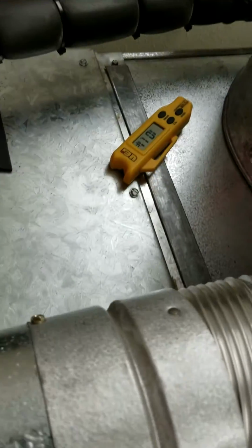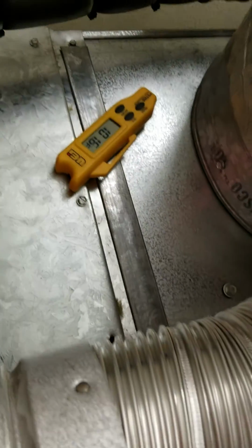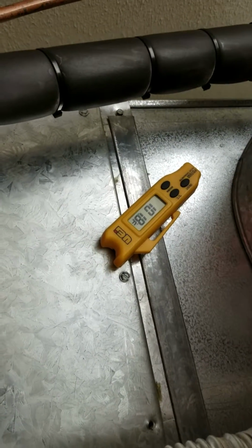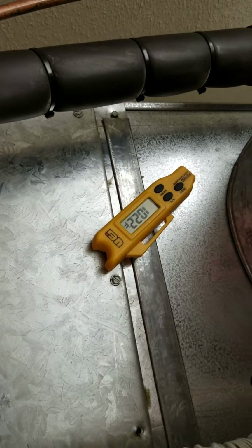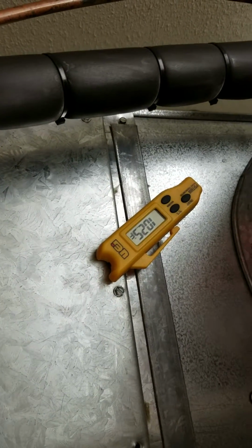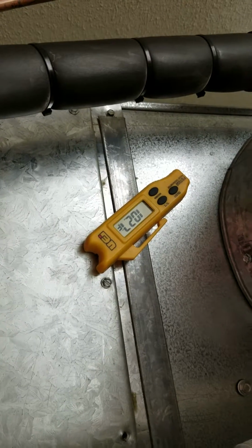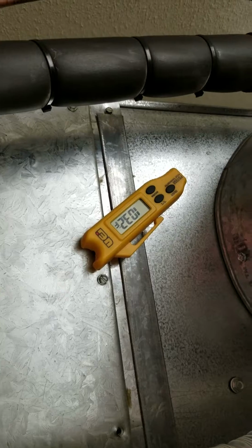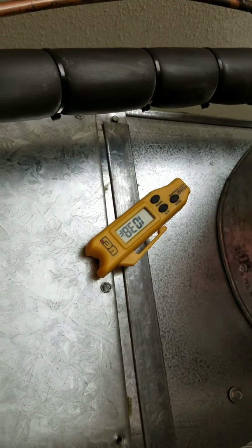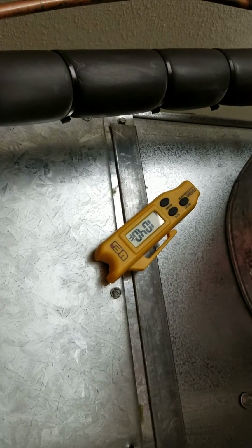Alright, so now we're checking our temperature rise. This particular furnace, if I remember right, is between 30 and 60 degree temperature rise. Our temperature in the room started out at 70. We are looking for no more than 130 degree discharge air. This is an indication of whether our furnace is fired correctly or not.